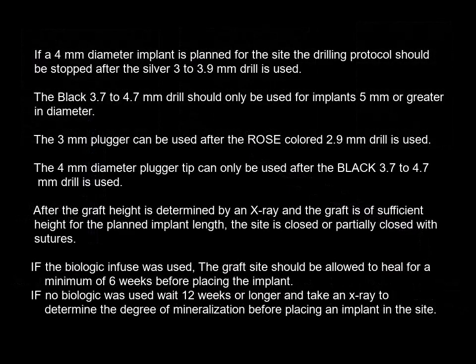If a 4 mm diameter implant is planned for the site, the drilling protocol should be stopped after the silver 3 to 3.9 mm drill is used. The black 3.7 to 4.7 mm drill should only be used for implants 5 mm or greater in diameter. The 3 mm plugger can be used after the rose-colored 2.9 mm drill is used. The 4 mm diameter plugger tip can only be used after the black 3.7 to 4.7 mm drill is used.